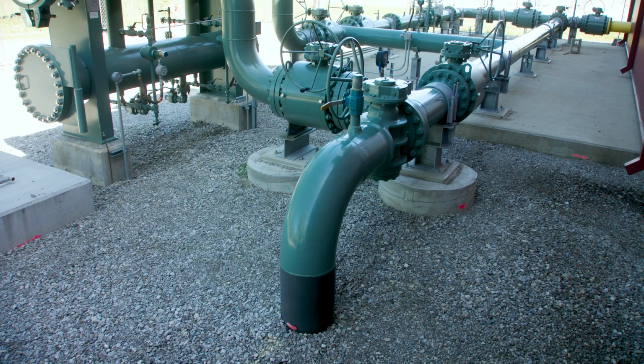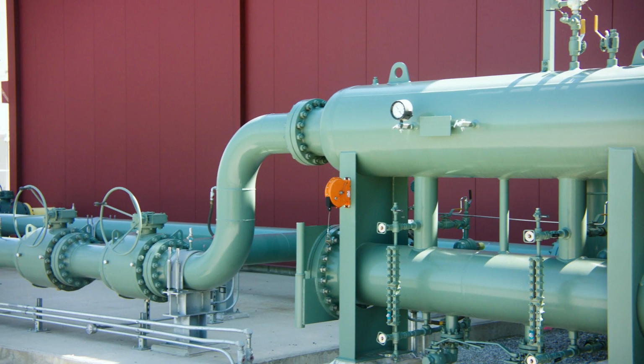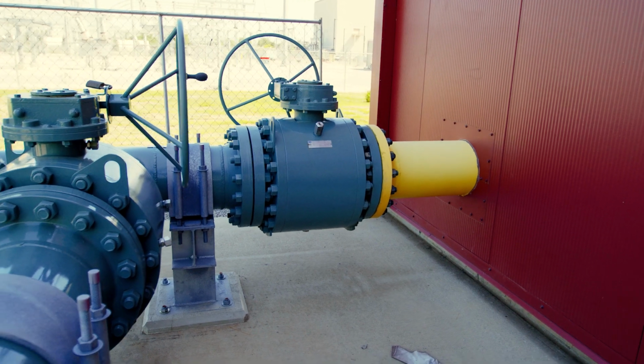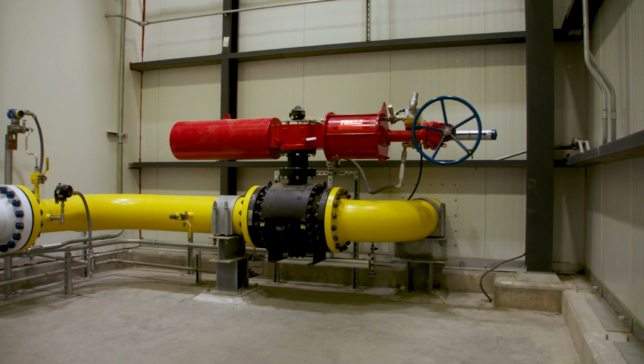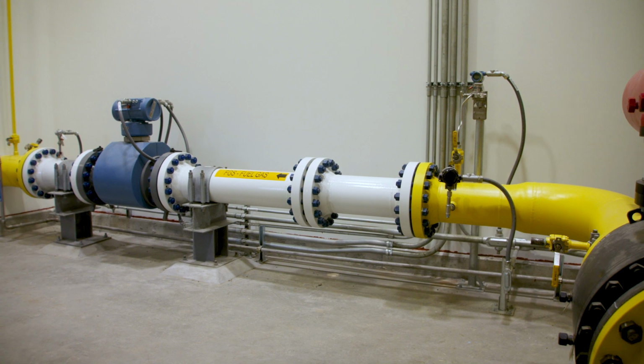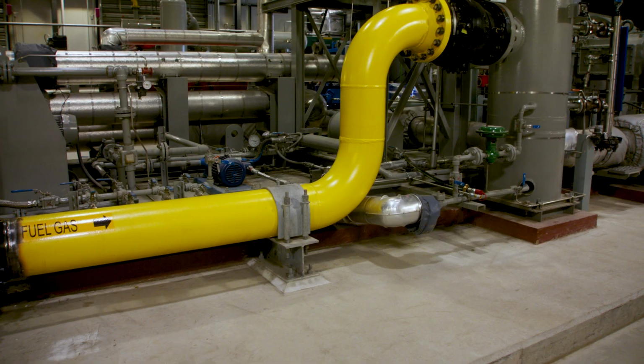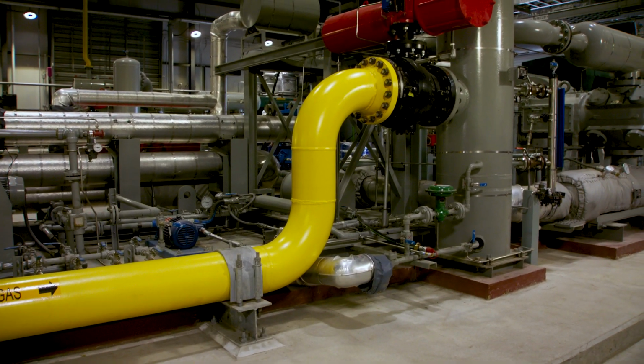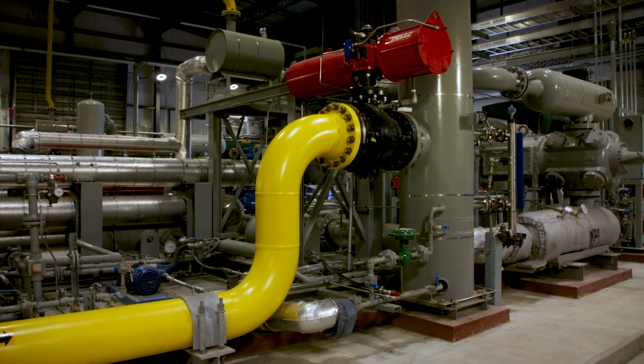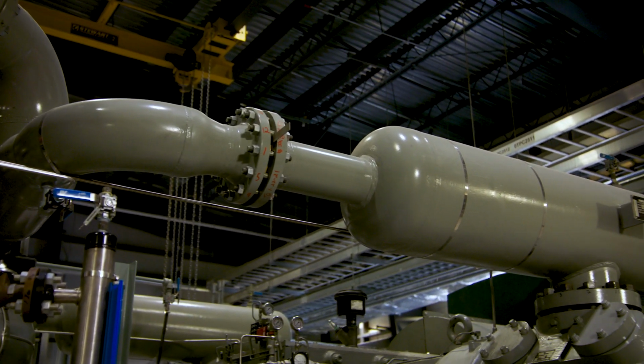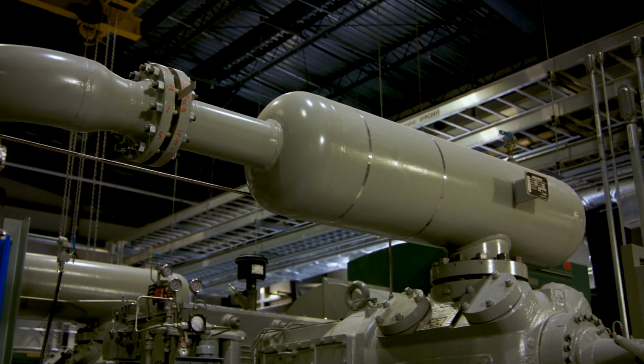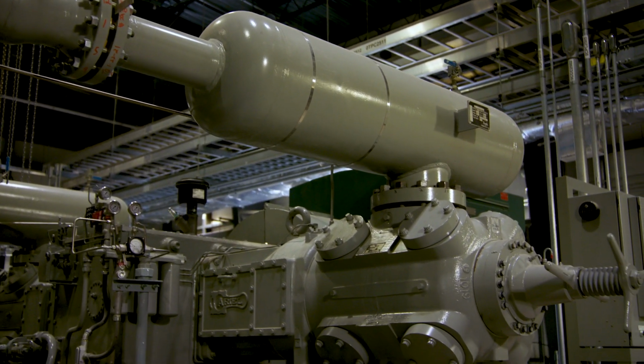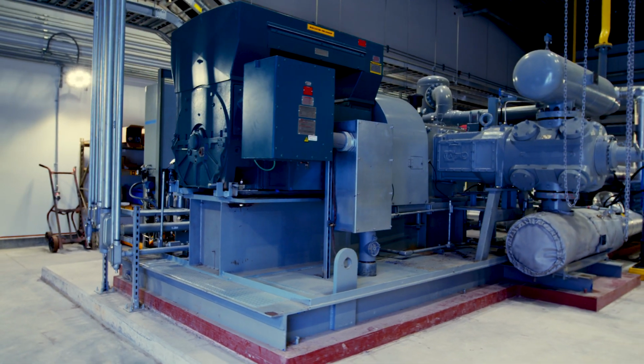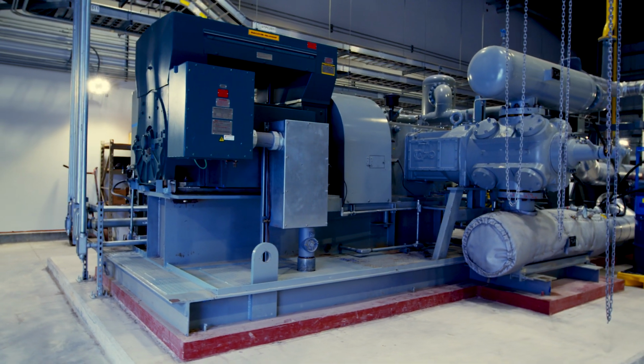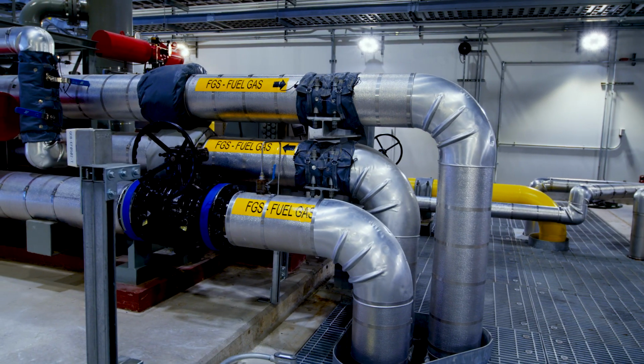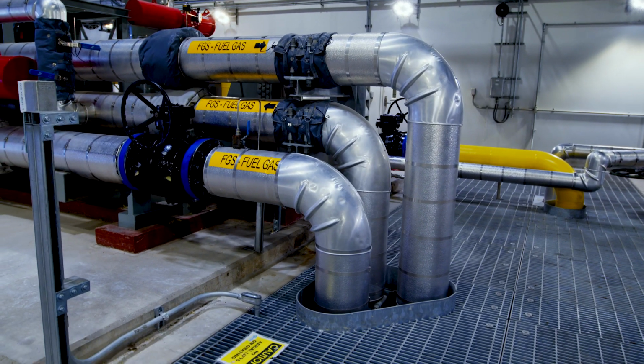At Delta Energy Park, the whole process starts with clean pipeline gas coming into DEP's compressor building. Here, 3 compressors take the gas from 350 pounds per square inch in the pipeline up to 500 pounds. Compressing the gas adds heat and increases efficiency in the Siemens SGT-800 turbines. Only 1 compressor will be needed to run the system on a typical basis, so the additional compressors provide operational redundancy and maintenance flexibility. Compressed gas then runs in a pipeline underground.